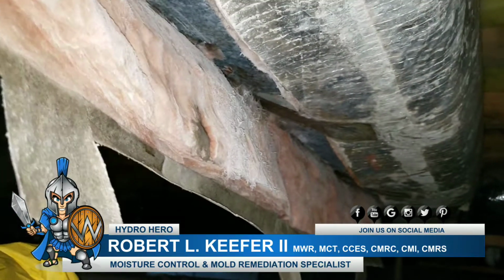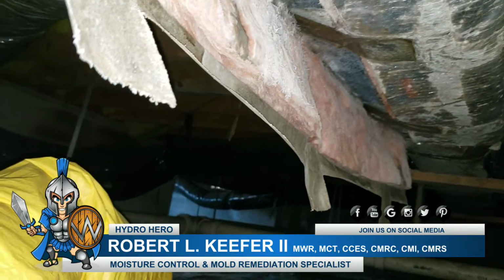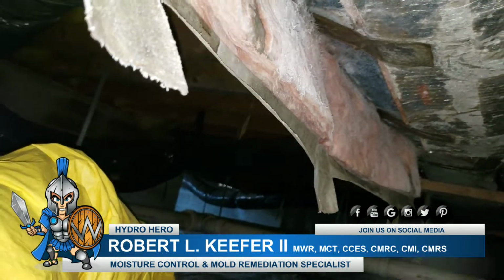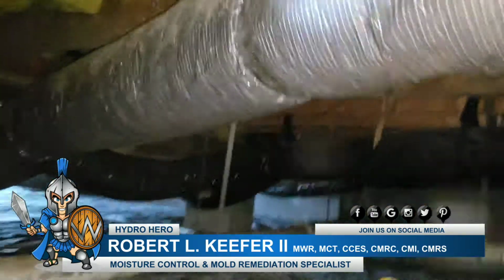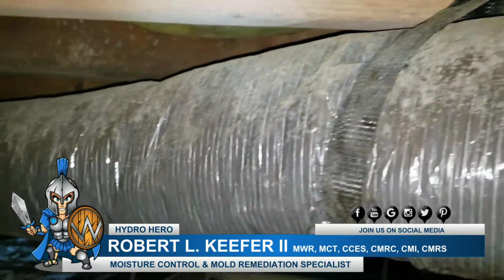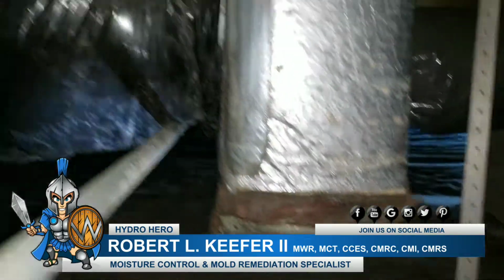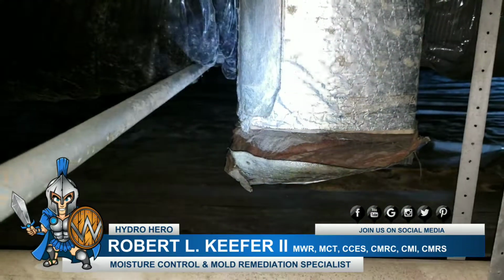Now, what you also see is that it's causing the HVAC system insulation to come apart. So now the HVAC's having to run harder than it should. You can see that mold is growing on top of the flex duct. Tape again is coming apart. More mold growing there.